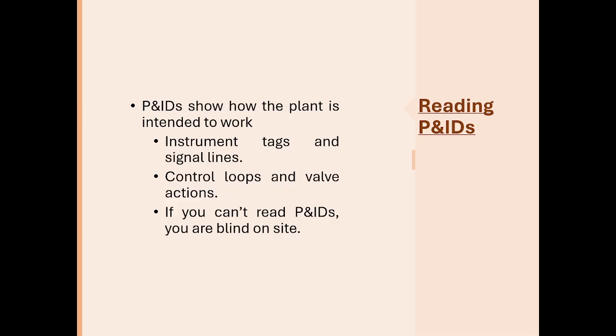Okay, so before you step on site, there is one drawing you must be comfortable with, which is the P&ID. P&ID stands for piping and instrumentation diagram, and it is not a wiring diagram, and it's not a layout drawing. It is a functional drawing that explains how the plant is intended to operate. On a P&ID, you will see pipes, equipment, instruments, valves, and signal lines. You will also see instrument tags that tell you what each device does and how it is connected in a control loop.